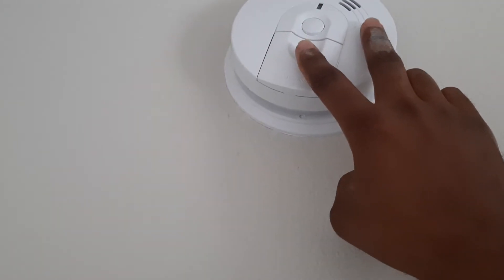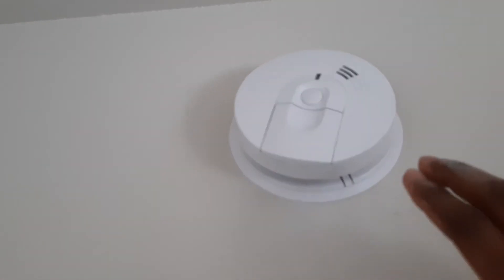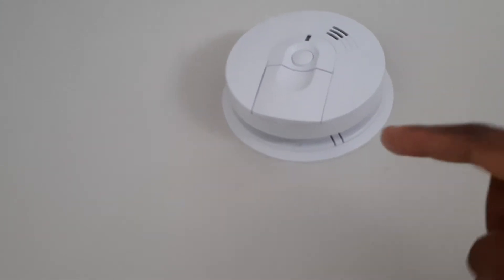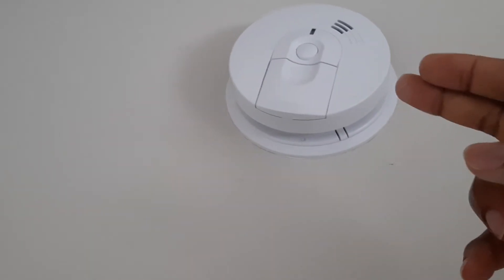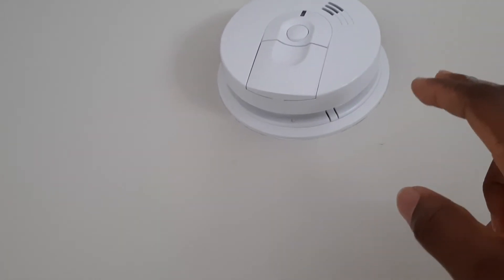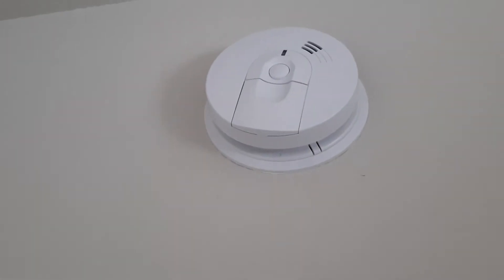Because the plates are electrically charged, the air between them is ionized and causes the flow of current between the two plates. When there is a buildup of smoke, chemicals in the air, or dust, it prevents the flow of current and causes the alarm to go off.